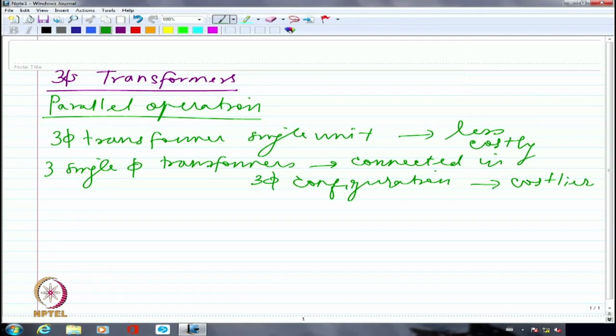You have more flexibility, clearly. So because of which you may not be able to save on the core cost or the stamping cost or even the winding cost in all probability. So this is generally used whenever I'm going to have extremely large rating. When I have very, very large rating and I want to retain the flexibility to connect it in either star or delta configuration.